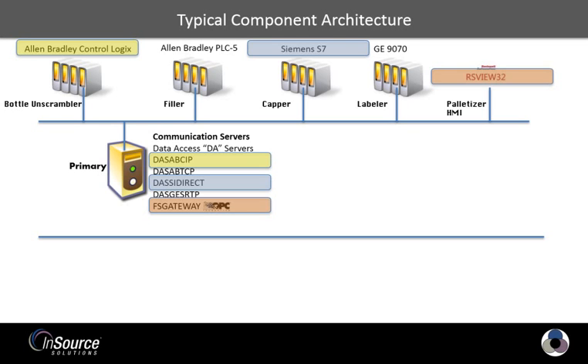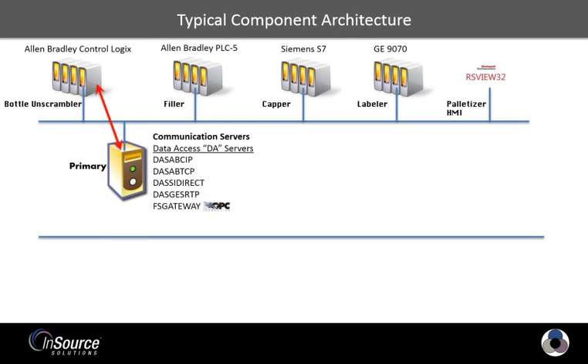Note that all these DA servers can coexist on the same PC, and a single Wonderware DA server license will enable them all. We're showing the data access servers on separate PCs here for clarity, but they can coexist with other Wonderware applications on the same PC, especially for smaller systems. Note also that each DA server can manage communications to multiple PLCs in the same family. Once the DA server has been configured with essential data like the TCP/IP address of the target PLC, it only establishes a passive connection to the PLC and is requesting only minimal data at this point. The DA server is waiting for a requesting application to ask for data in a specific PLC, and then will poll the PLC for this data based on the poll rates configured in the topics.